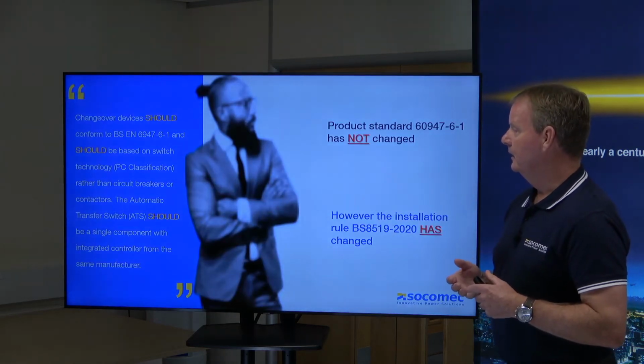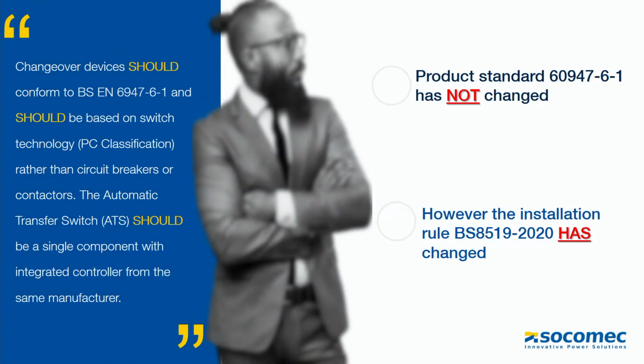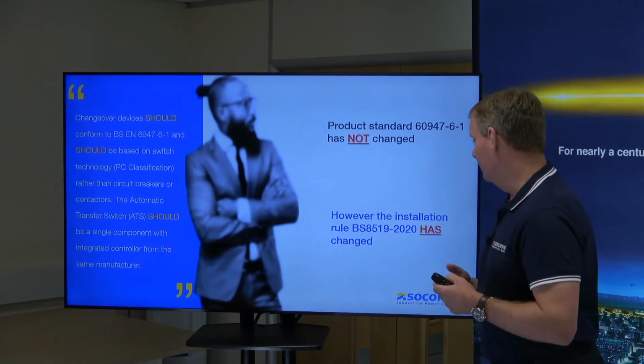So just to run through and clarify all what we've discussed this morning. Changeover devices should conform to BS EN 60947-6-1 or IEC, and should be based on switch technology PC classification rather than circuit breakers or contactors, which means it must. And the automatic transfer switch or ATS should be a single component with an integrated controller from the same manufacturer.